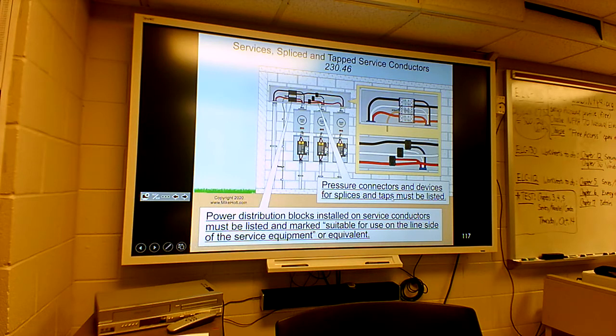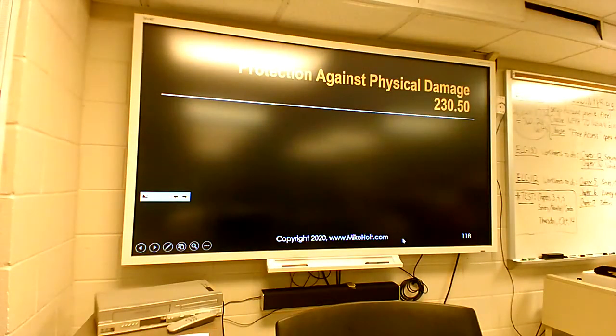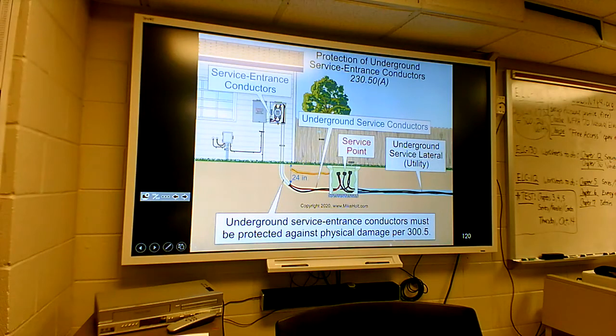Power distribution blocks installed on service conductors must be listed and marked as suitable for use on the line side of service equipment or equivalent. So that all boils down to something that needs to be store-bought and approved and listed, not a homemade thing. And protection against physical damage underground. Now here they got a box. So they've got like a PVC box of some type, and they've got their splices that are underground, but they've got a box that's like a watertight box that's listed for that. And it looks like they've actually got some cement or some rocks under that box.